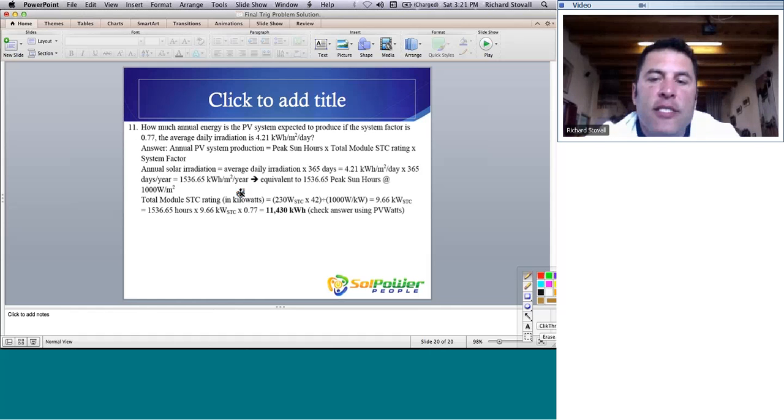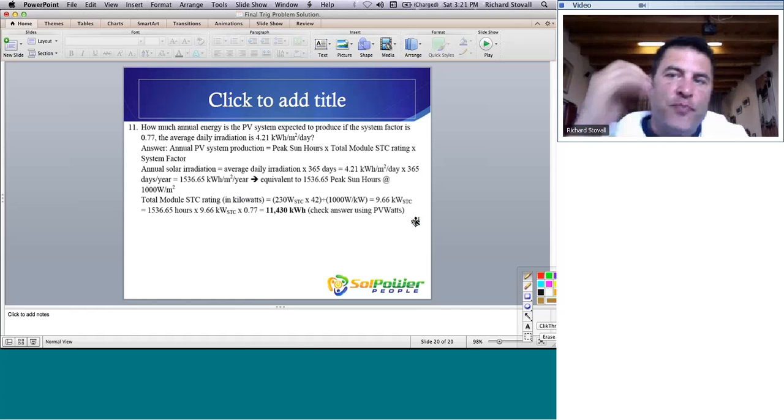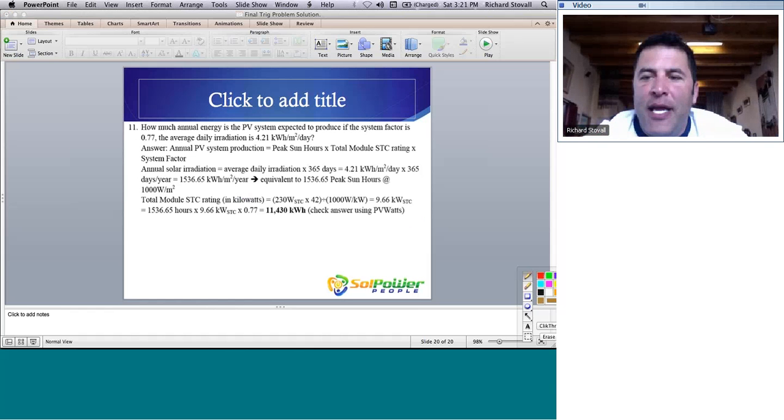So we take the 230 watts times 42, and we get a 9.66 kilowatt system. Then a 9.66 kilowatt system times that number of hours times the derating factor of 0.77 is 11,430 kilowatt hours. You can check that against PVWatts. But this is very much in line with the problems that we worked out earlier. Probably a bit less complicated than what we did earlier with the retired NABCEP exam questions.